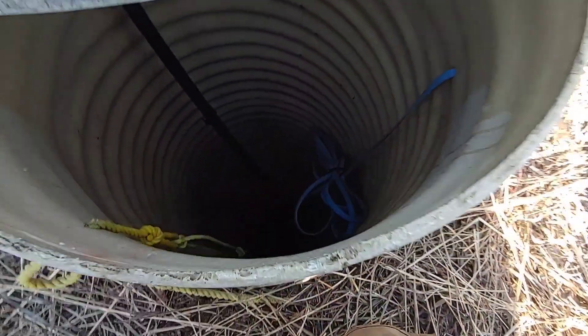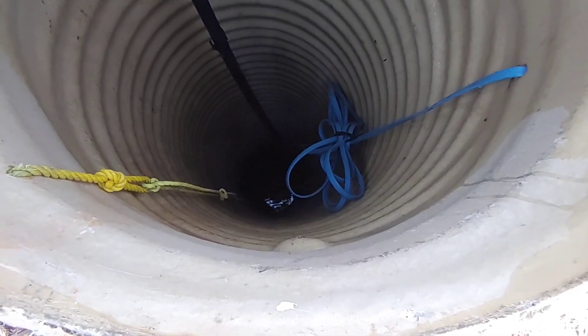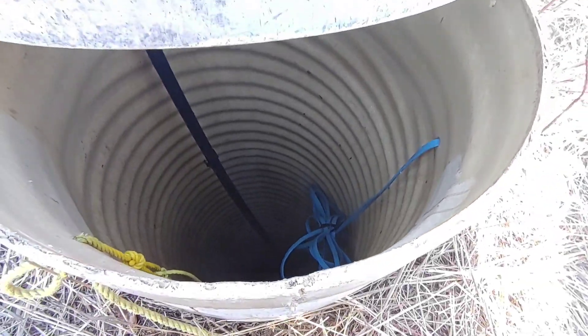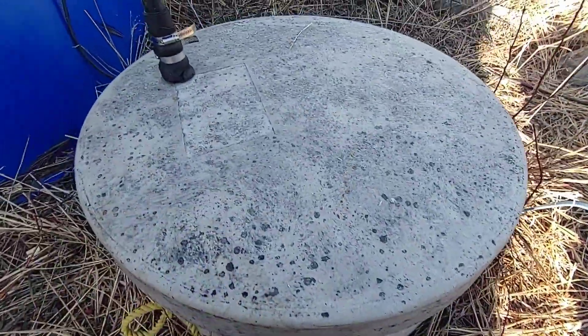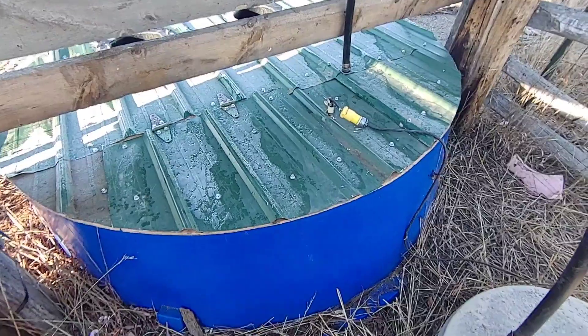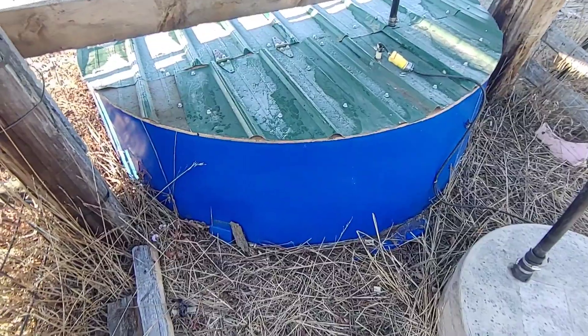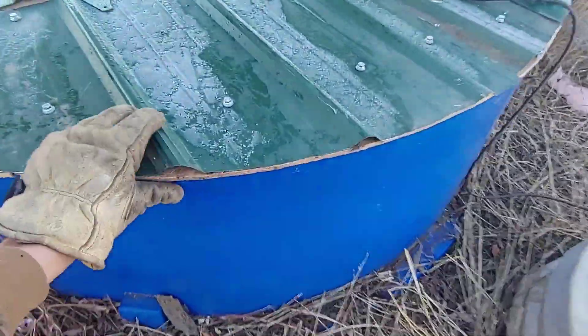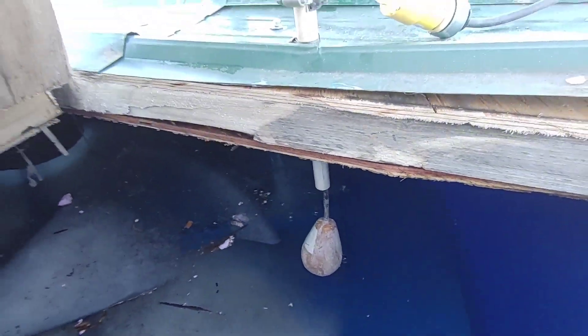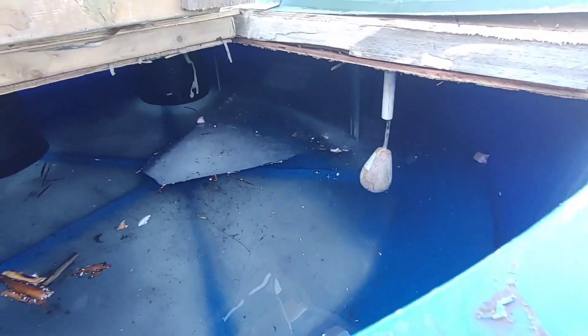That pump is actually down here in a bored well, not quite 40 feet deep. Water is about 12 to 13 feet down, and it's actually gone down about 4 feet since we started pumping. We haven't pulled out of this well in quite many years, because the solar technology 20 years ago when the well was drilled was not spectacular. This is the insulated trough — insulated on the bottom and sides with a drain plug. I just finished building this lid: it has tin, plywood, and styrofoam insulation sandwiched between two layers of plywood with tin on top. You can see the stream of water coming in, running about 7 to 8 gallons a minute.